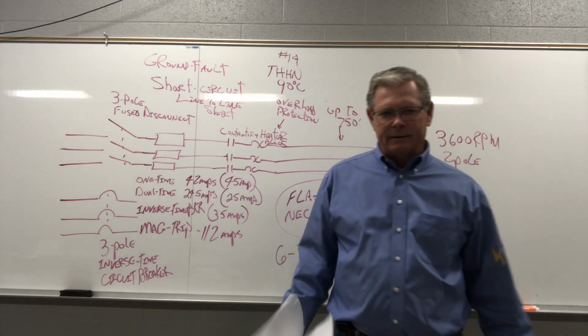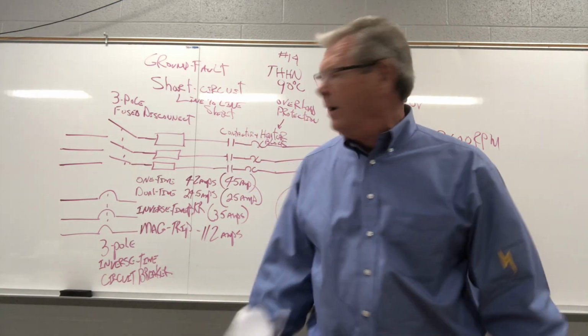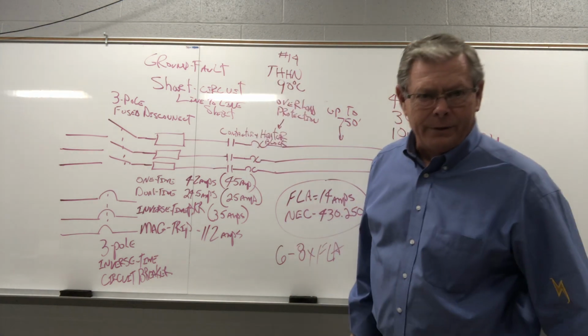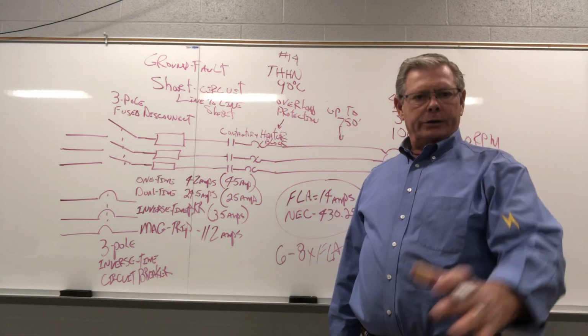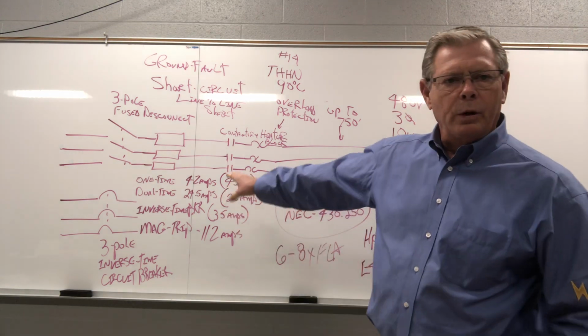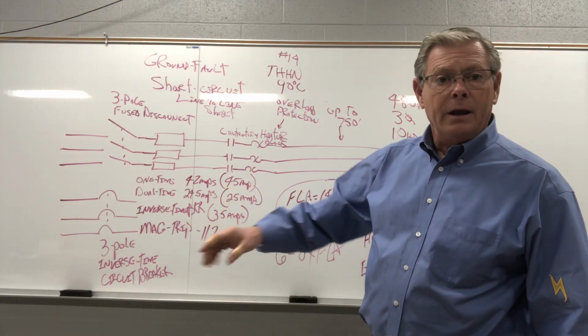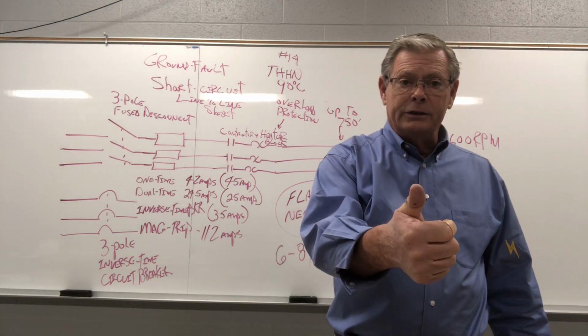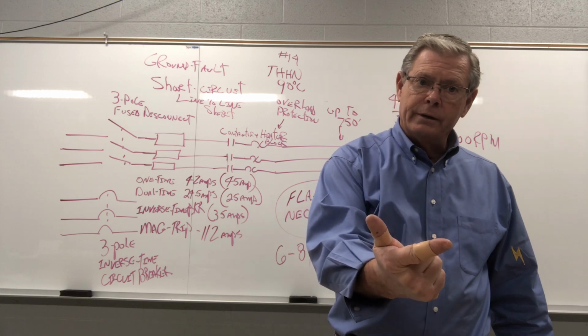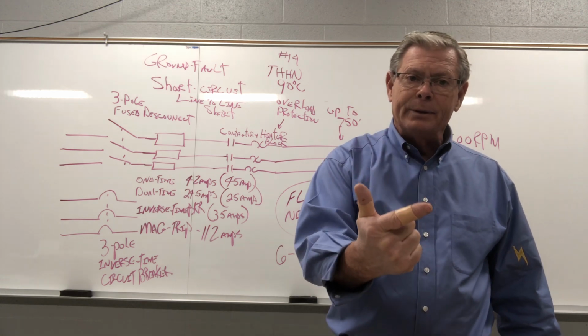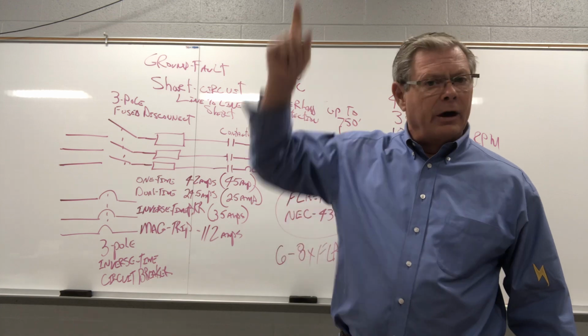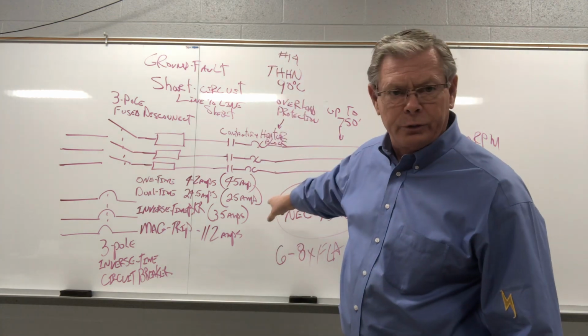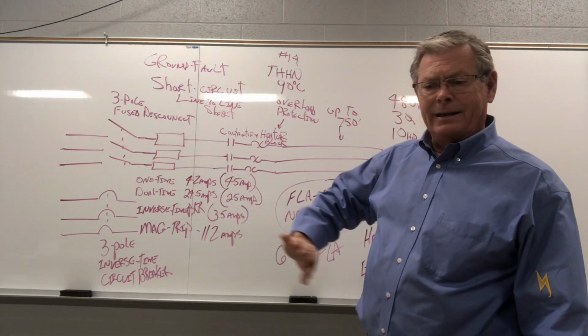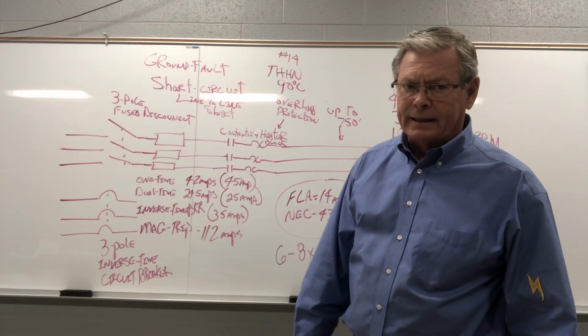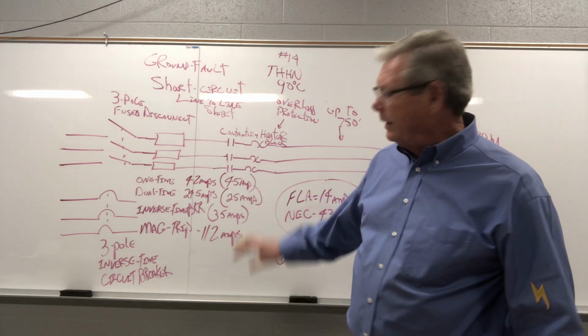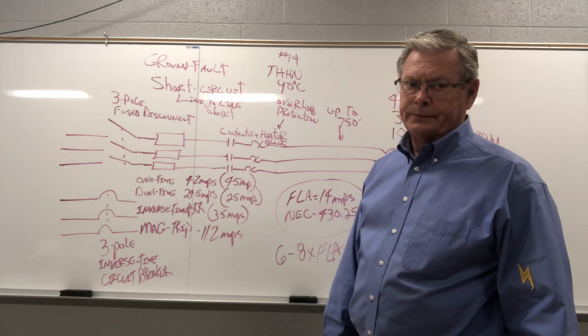Now that might sound like a lot, 112 amps. Wow, that's so much more than 14 wire is good for, right? Sure it is. But what's the job of the breaker or the fuses? It's line to line short, line to ground short. So when that happens, instantly that current goes through the roof. You blow through 112 amps so quick, many times quicker than you can blink an eye. 1 to 2 cycles, that's going to trip.